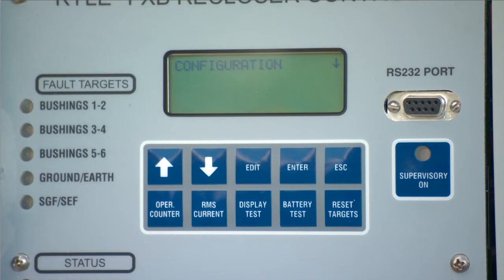The use of manual operation switches provides designated control commands to the recloser. The switches also provide an alternative to using a computer interface or scrolling through the LCD menus. Supervisory On. The Supervisory On feature is provided on controls equipped with the optional SCADA accessory. If the Supervisory On switch is on, it allows supervisory operation of the control. Conversely, if the Supervisory On switch is not on, it prevents supervisory operation of the control.